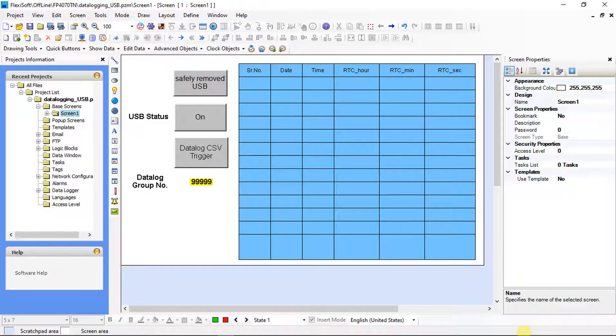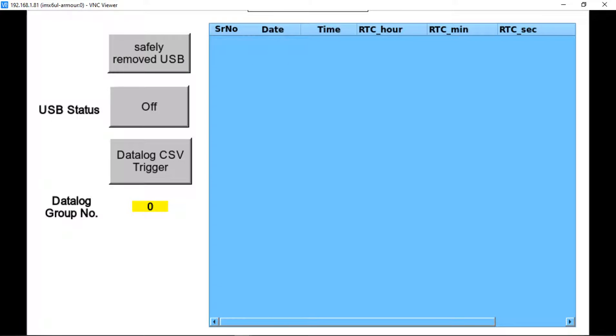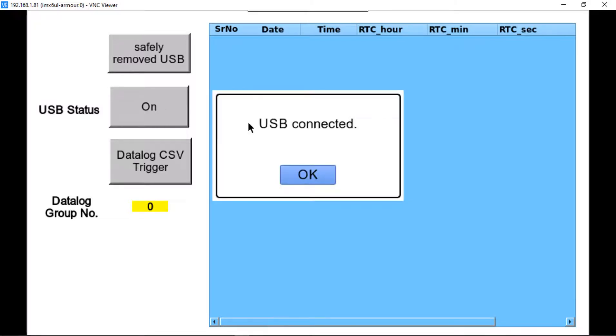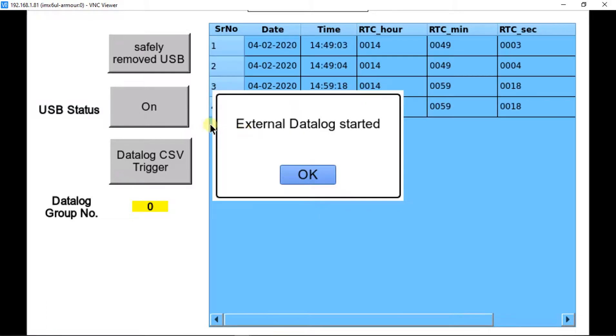In this way we have completed data logging configuration using external memory. For demonstration purpose we'll use VNC viewer software; you can directly check on the hardware. For more information about opening VNC viewer screen, please refer the VNC server video. This is our HMI screen — data logging is not started yet as USB is not connected. USB status is also off — connect the USB stick. USB connected message is on screen and data logging is also started.